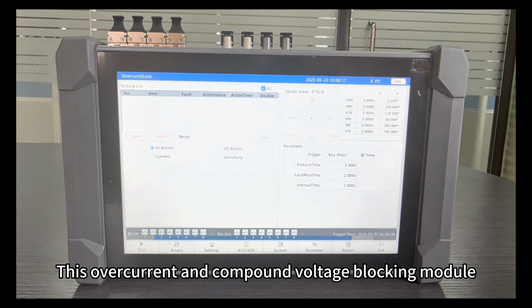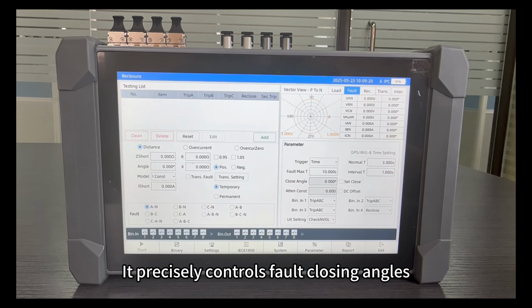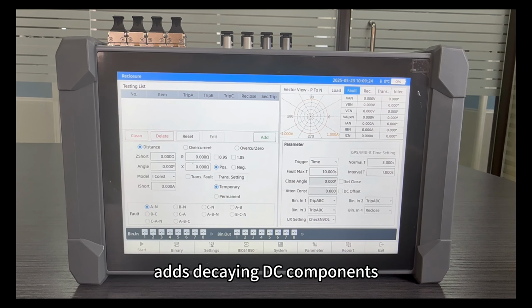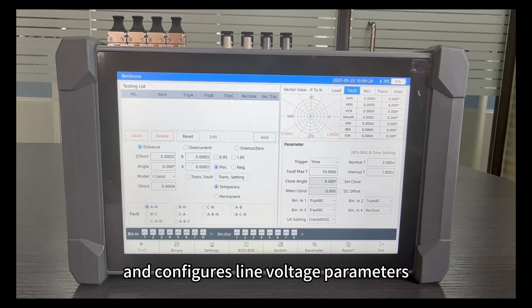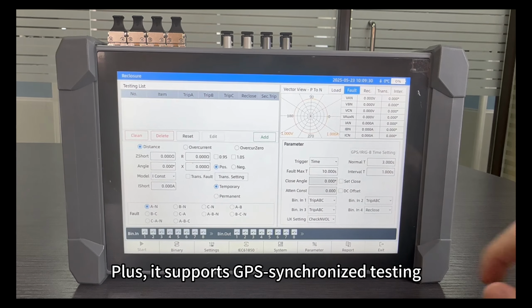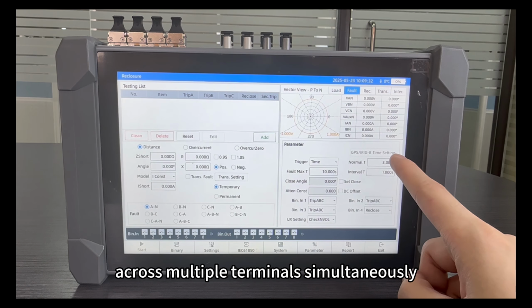The reclosure module tests integrated protection systems, including overcurrent, distance, zero sequence and reclosure functions. It precisely controls fault closing angles, adds decaying DC components, and configures line voltage parameters for synchronization verification. Plus, it supports GPS synchronized testing across multiple terminals simultaneously.